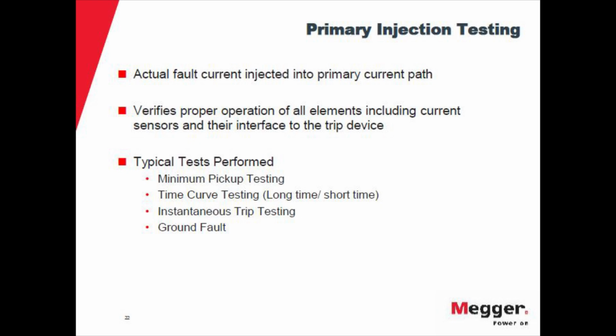Primary injection testing is basically that you inject actual fault current into the path of the breaker, and you wait for the breaker to operate according to the manufacturer's characteristics. This verifies the proper operation of all of the elements, including the current sensors that you mentioned before and the interface to the trip device. So everything is checked, in addition to the entire primary path.